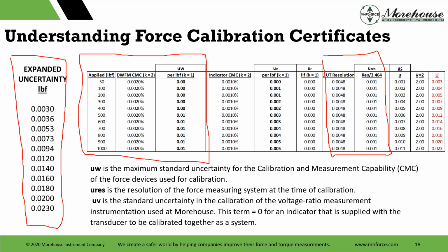And we're going to divide by the appropriate coverage factor, which in this case is the square root of 12, which is 3.464. A lot of good information on uncertainty distributions can be found in UKAS M3003. And UV then is the standard uncertainty in the calibration of the voltage ratio measurement instrumentation used at Morehouse. We were using Fluke 8508s and Agilent 3458s, 10 volt, 5 volt DC excitation, either one. And then we have complete traceability on this standard. If someone sends us an indicator with the system, then this term becomes zero because we treat everything as a system cal. When you send a complete system, the total uncertainty is a lot less. There's less to do as far as demonstrating metrological traceability, because when you do not send that indicator, you have to make sure your indicating systems are traceable as well.